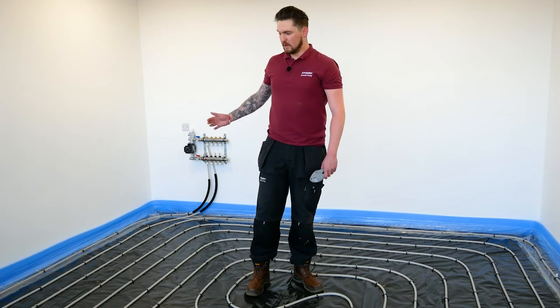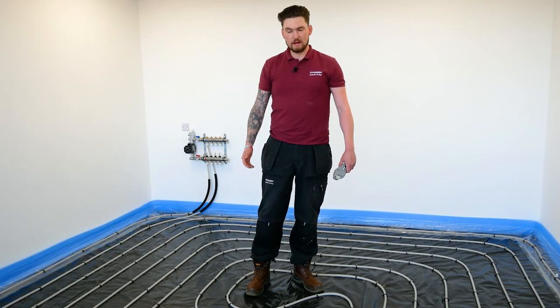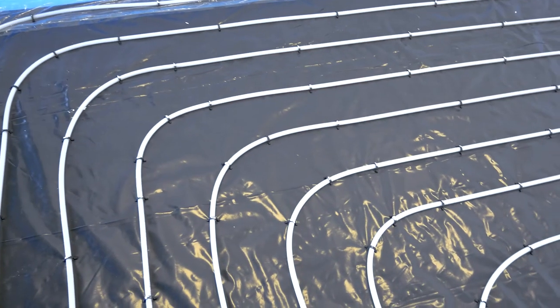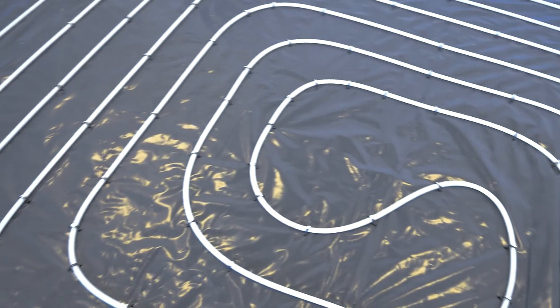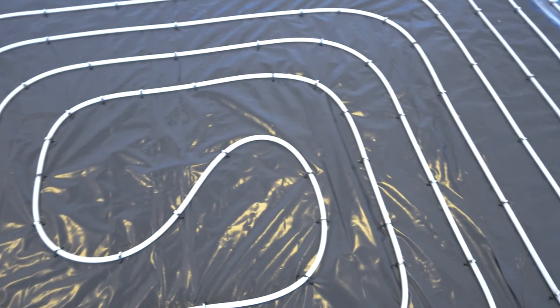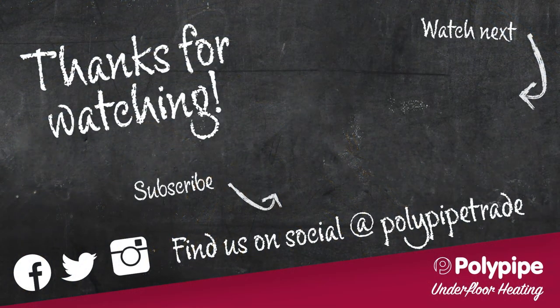As you can see, we've laid the circuit in a bifilar pattern, more commonly known as a spiral pattern. We've laid it at 200mm centres, and it's worth noting that when we've come around a 90-degree bend, we've had to put a couple of extra staples in here and there to ensure that we maintain the bend radius and it doesn't misshape or misform. For further information on the staple system, please refer to our installation guide.